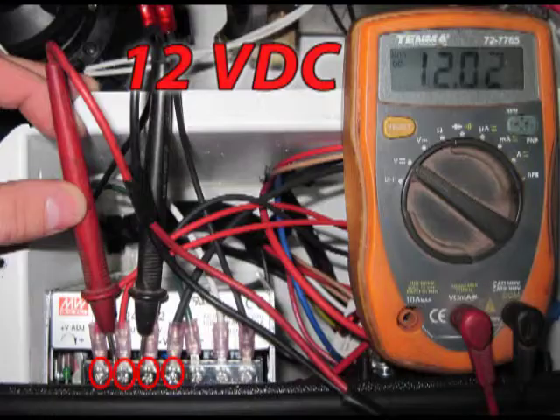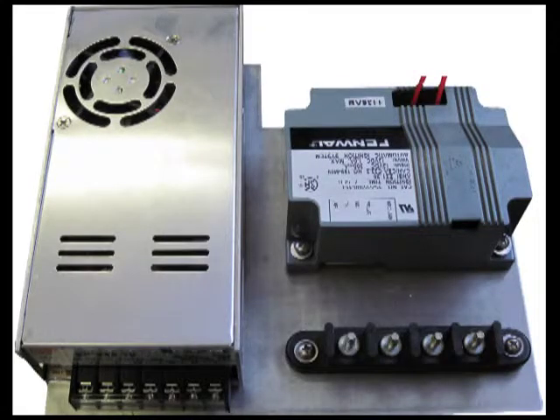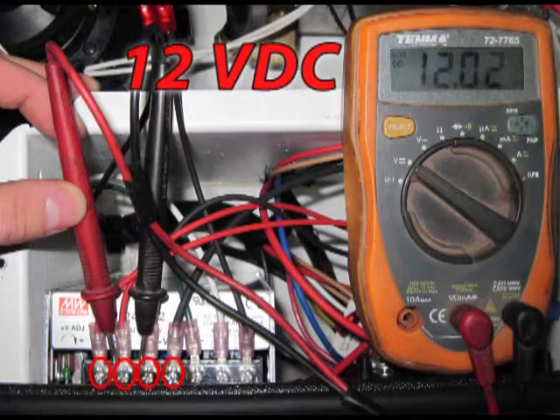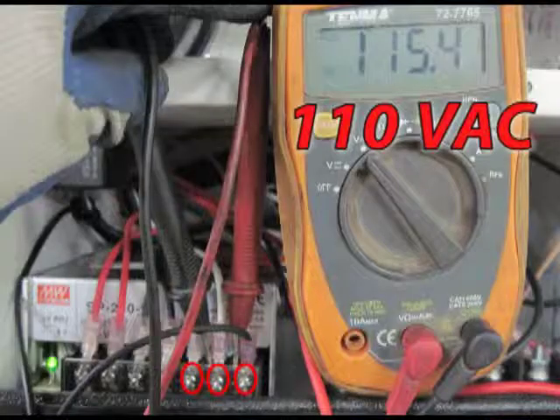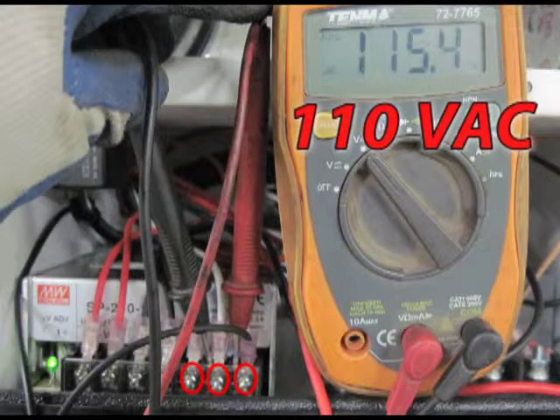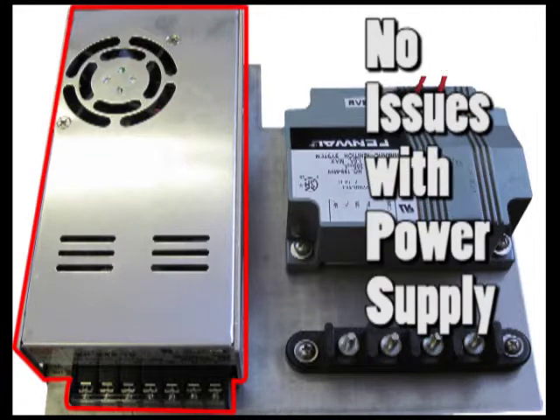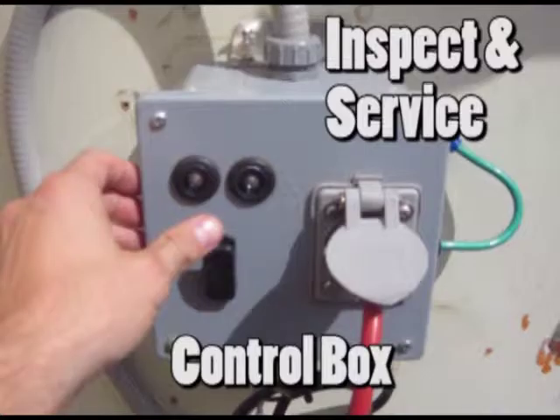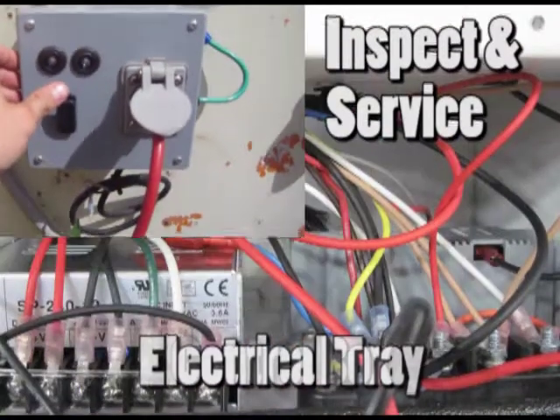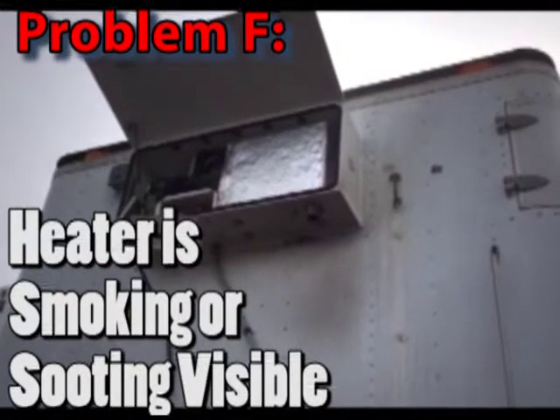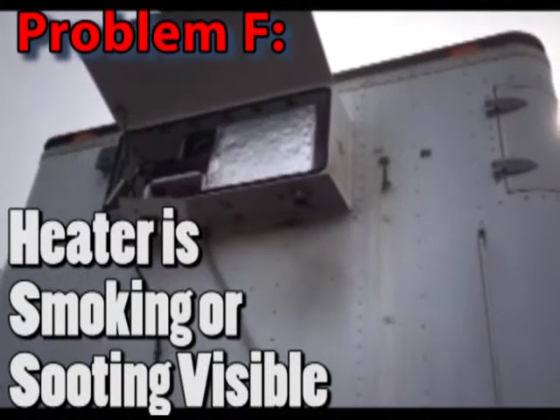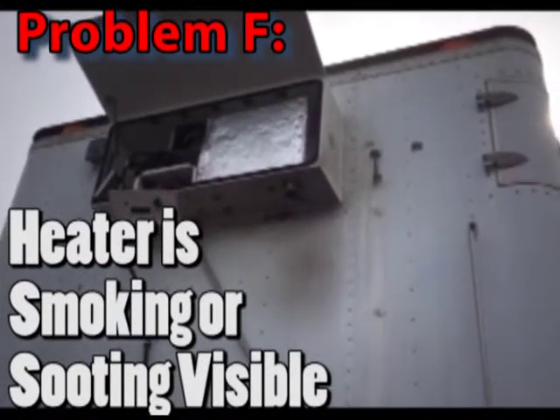across all 4 terminals. If the power supply isn't outputting 12 volts DC across all 4 terminals with proper 110 VAC input, the power supply needs to be replaced. If you do not find any problems with the 110 VAC power supply, the control box or the electrical tray assembly needs to be inspected and serviced. Problem F. The heater is producing smoke or carbon deposits are visible near the outlet of the heater.